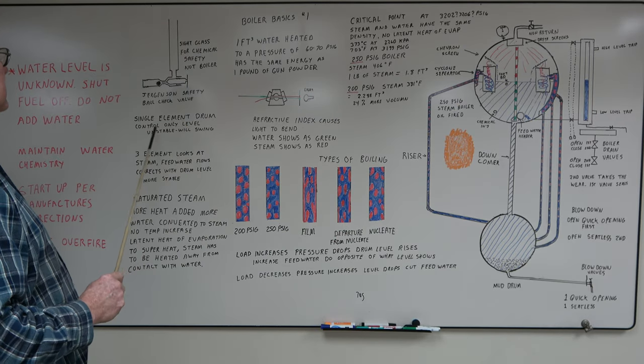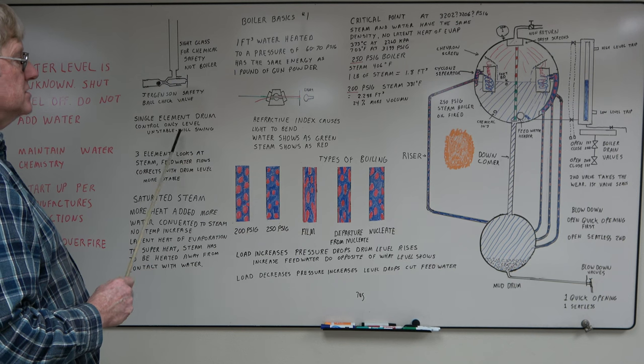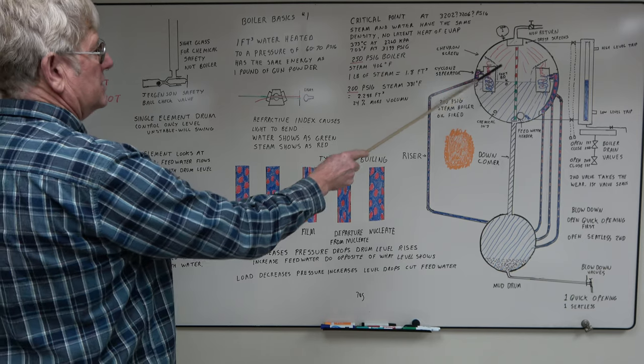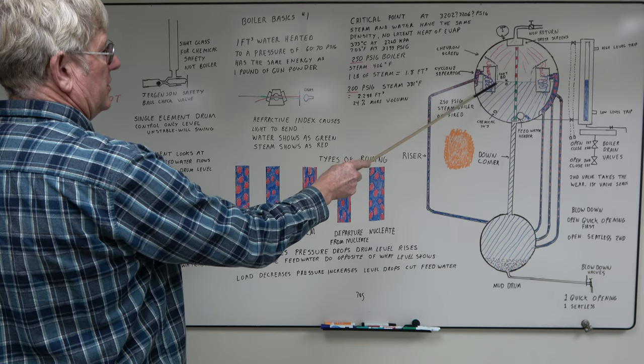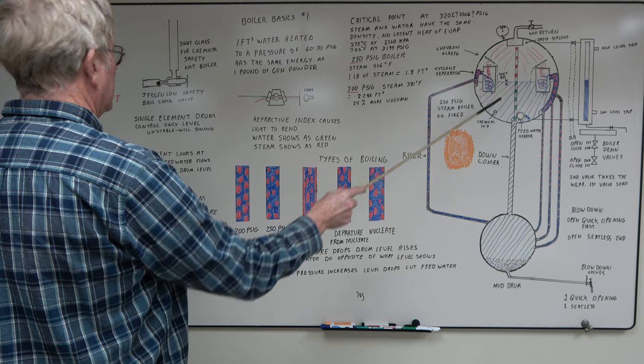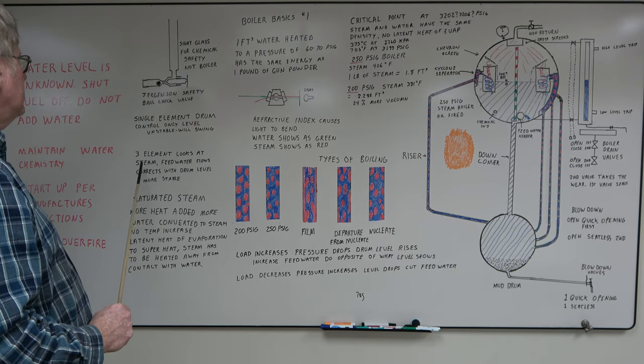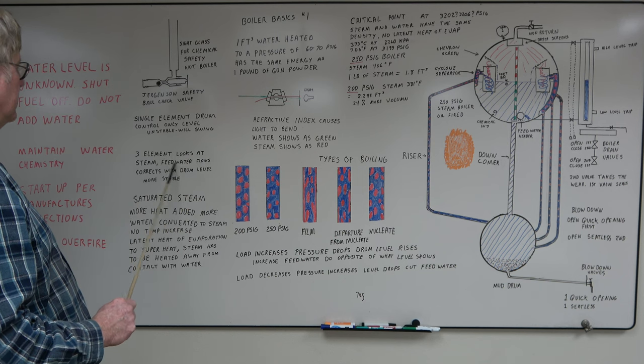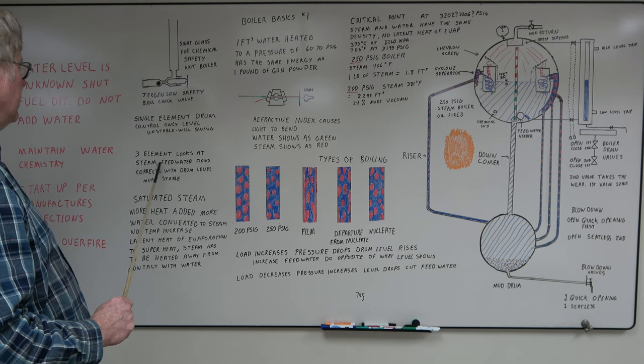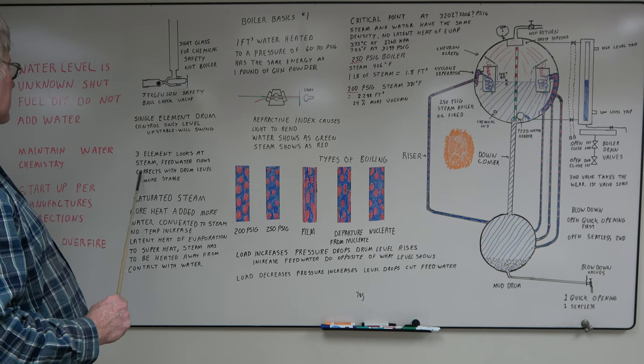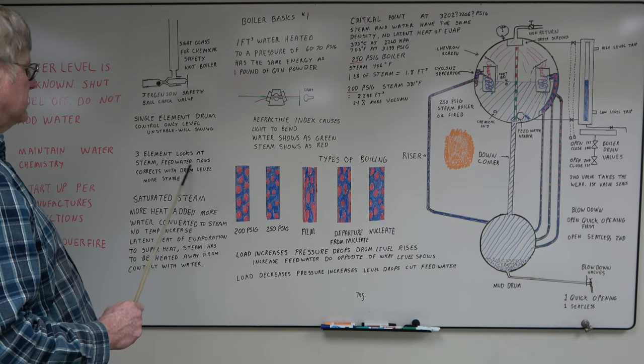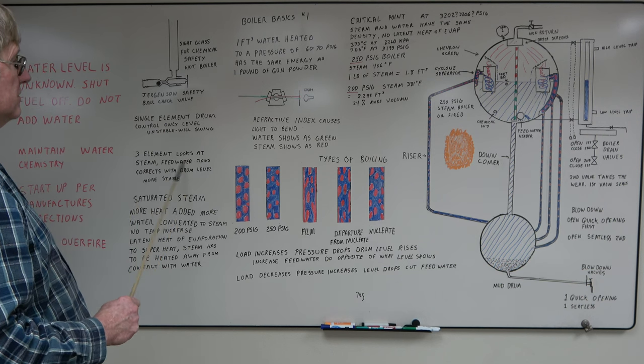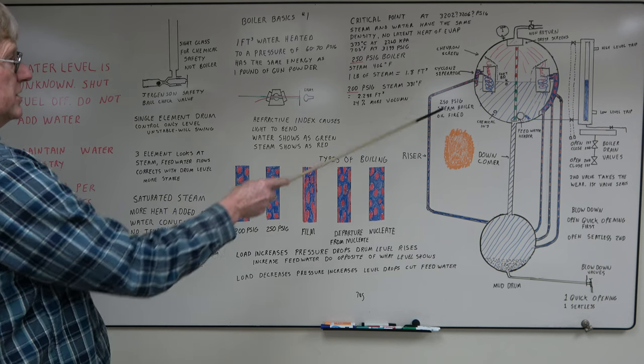A single element drum level control only looks at level. It's fairly unstable and these kind of problems you're going to see. As soon as this level goes high, it's going to shut down the flow. You're going to get back to normal. Unless the pressure comes up, now you're going to really drop. The three element that looks at steam and feed water flows, it tries to balance the steam flow with the feed water flows. It's a forward looking type controller. It corrects with the drum level. It's a lot more stable. If it sees a high steam flow increase, it's going to kick up the feed water and it'll correct the drum level. It takes a lot of this swinging problems out.